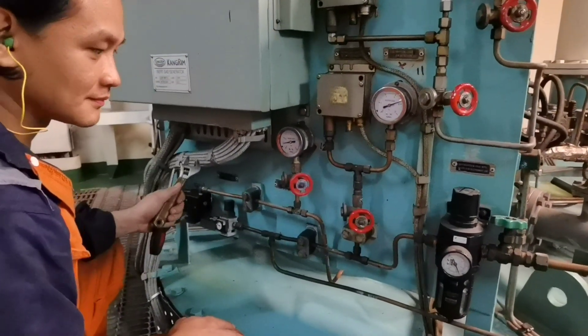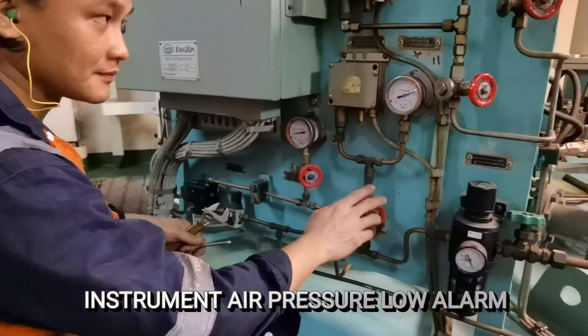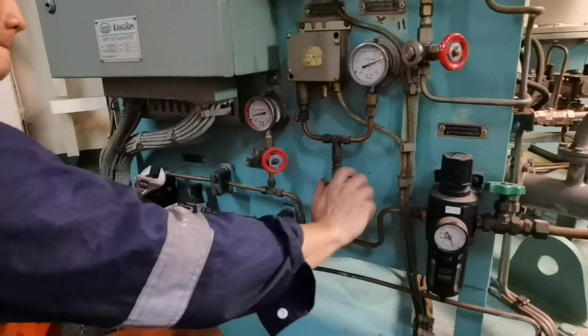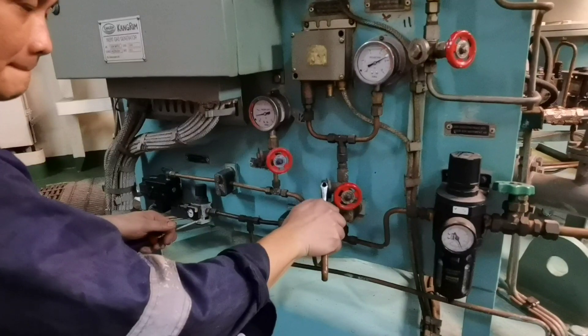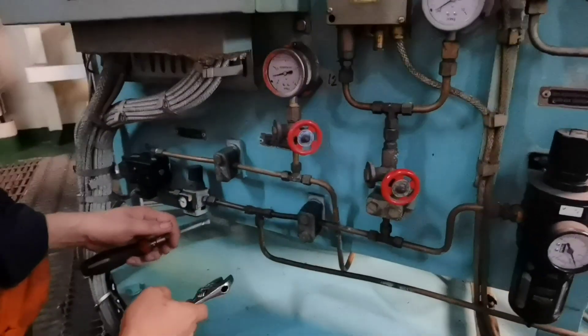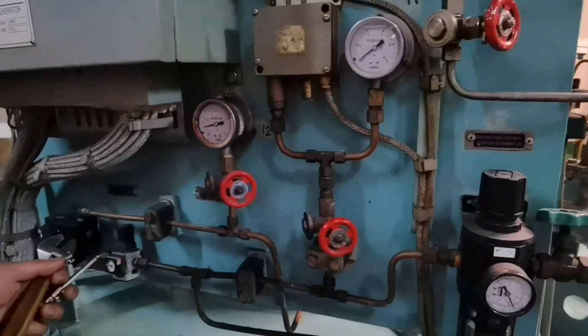Our first alarm for IG is instrument air pressure low alarm. What we'll do is close the inlet pad pressure switch and open the drain. We'll open the drain, so the alarm will come.